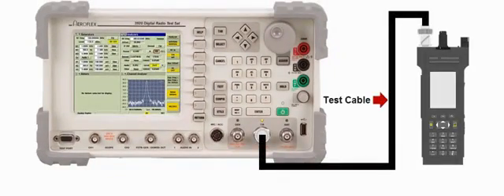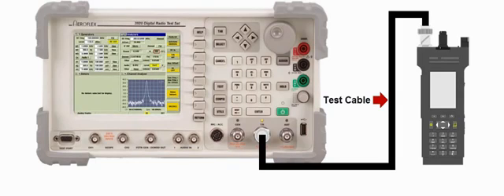In order to obtain an accurate power measurement, the loss of the test cable must be factored into the test.